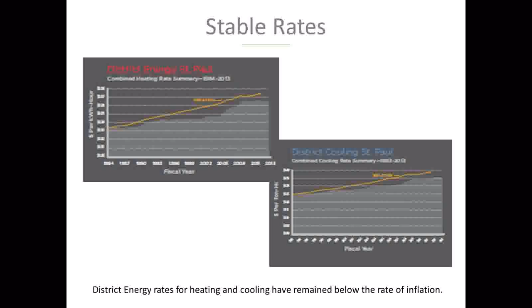One of the technologies we've integrated is thermal storage. We have two chilled water tanks. This is the largest, just over 4 million gallons. We have another, a little over 2 million gallons, located closer to the larger plant. This allows us to produce chilled water at night, moving about 9 megawatts off peak from day to night, a great cost savings for customers and a great benefit to the electrical grid. It acts almost like a smart grid technology, storing thermal energy and releasing it during the heat of the day.